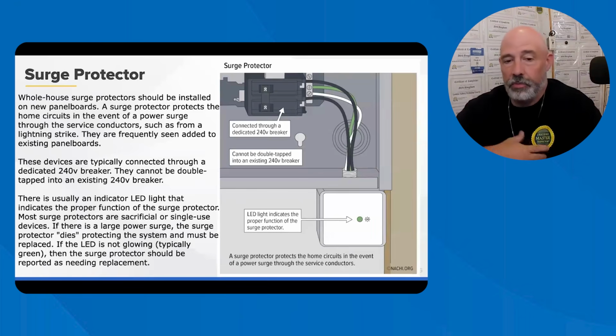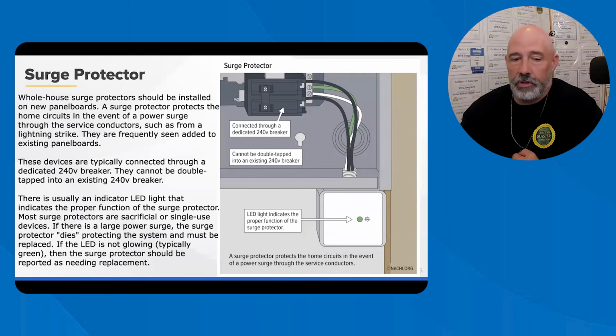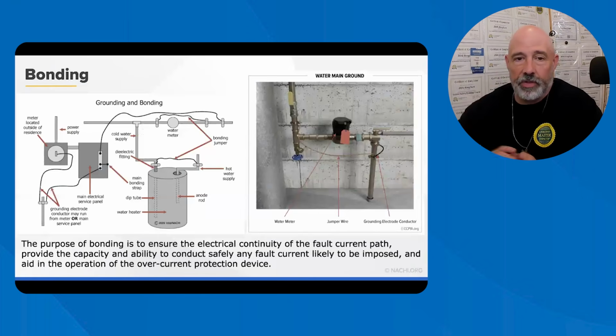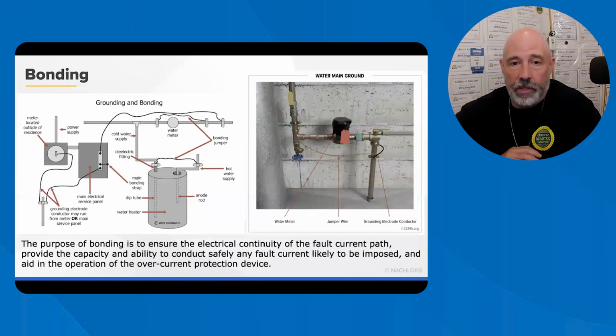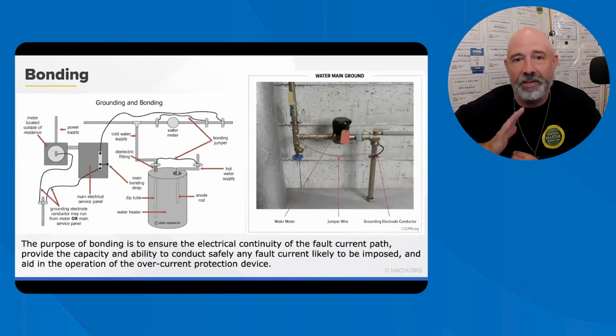Most units have an indicating light, so you can see whether it's working or not. I do recommend that when you do these inspections, you test those to make sure that they are working. As I like to say, it's a lot cheaper to replace a surge protector than an air conditioner, refrigerator, television. Some of those televisions are getting pretty spendy, and computers, of course. So you definitely want to have surge protection. Anyways, got off subject there for a second.